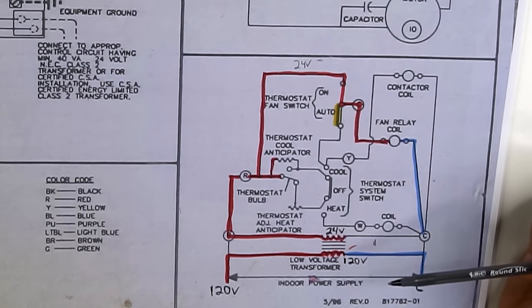Even though the fan motor doesn't have an overload symbol shown, notice it says IO on the fan motor — same as IO on the compressor. IO stands for internal overload. All fan motors and compressors have an internal overload installed in them. If the motor overheats, it will shut itself down to prevent burning out. For the 240-volt circuit, this wiring diagram is about as simple as it gets — and the low voltage was actually more complicated than the high voltage. So that was the ladder diagram.